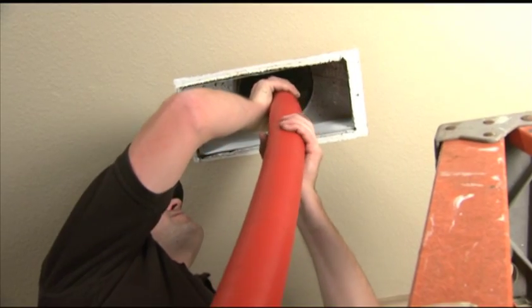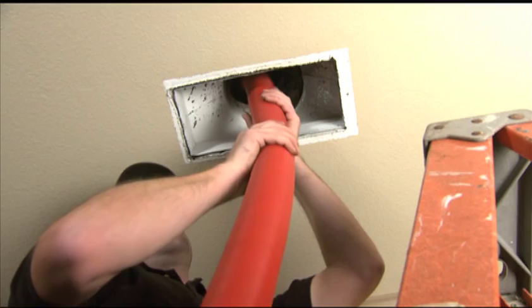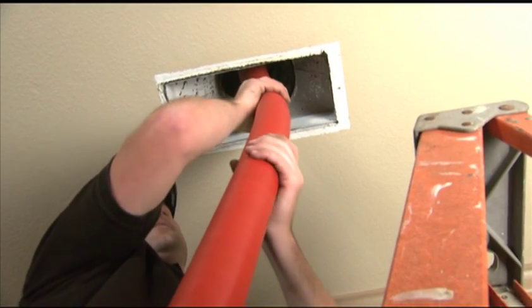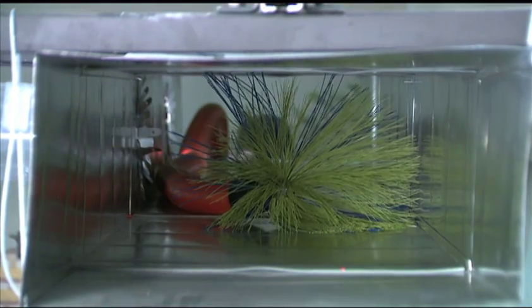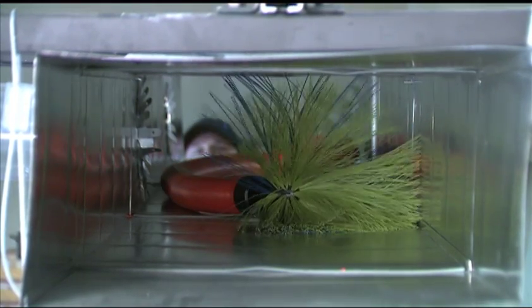second. Now, if you're cleaning rectangle ductwork, you need to use a sweeping method to assure you're cleaning all sides of the duct. You'll sweep the air duct by first inserting the brush and the hose all the way down the duct line. Then reverse the brush rotation to cause the brush to travel toward the other side of the duct. Pull the brush back about 6 inches and then reverse direction again. Repeat as needed to clean the length of the duct.